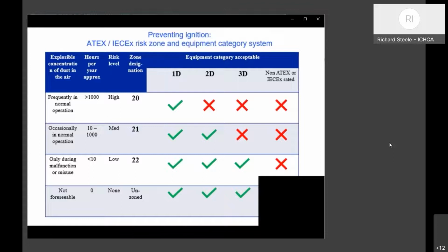If you have an area where you may get explosive dust in normal operation, but not very often, then we call that a medium risk or zone 21, and you can still use category 1D equipment. You can also use category 2D equipment, which has still significant protection against generating an ignition source, but not as high as category 1D.